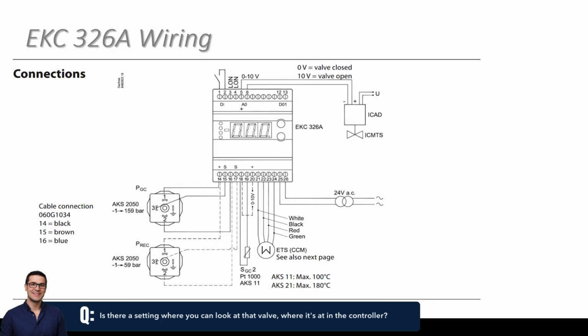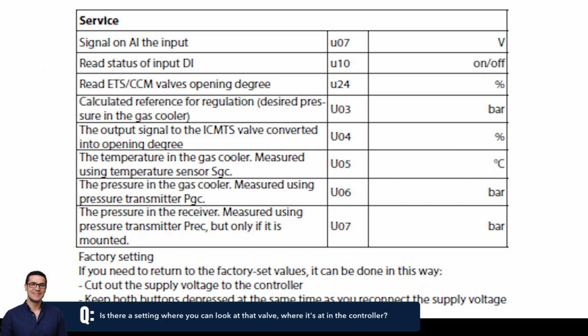Because that would be a key. If it says it's really supposed to be 70% open and it says 70 on the controller, but you know it's not 70% open, it could be the wiring of it. Yep. I'm going to bring another slide or screen in here just real quick.